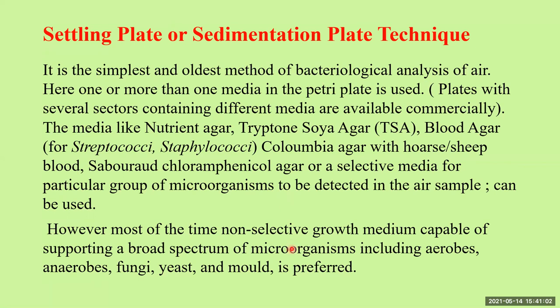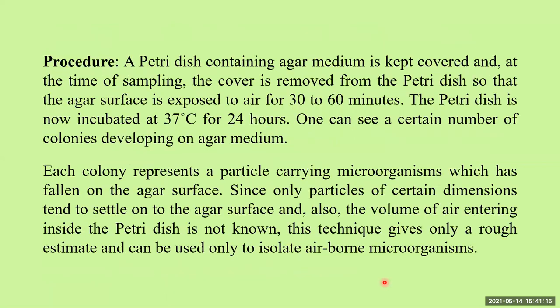Most of the time, a non-selective growth medium capable of supporting the growth of a broad spectrum of microorganisms — including aerobes, anaerobes, fungi, yeast, and molds — is preferred. The petri dish containing agar medium is kept covered, and at the time of sampling, the cover is removed so that the agar surface is exposed to air for a period of 30 to 60 minutes. The volume of air sampled is not known here because it is not connected to a sampler.